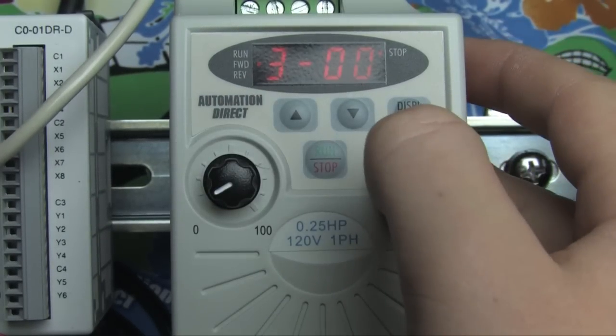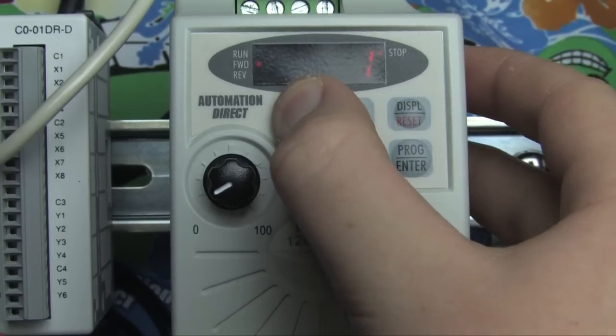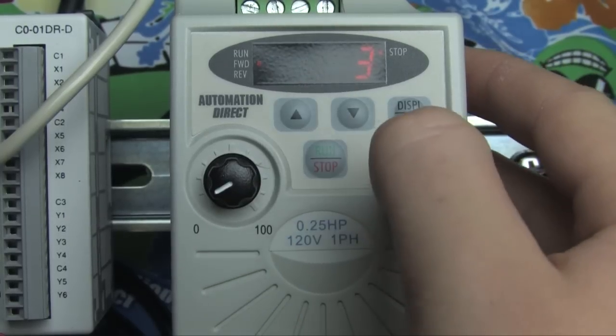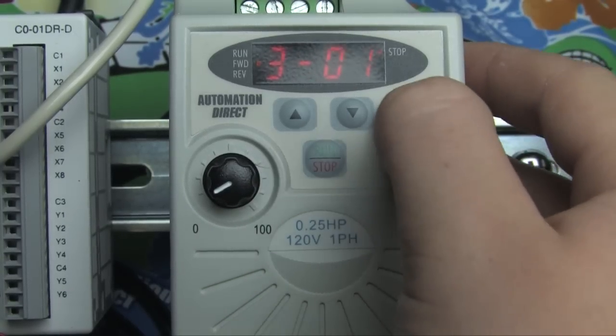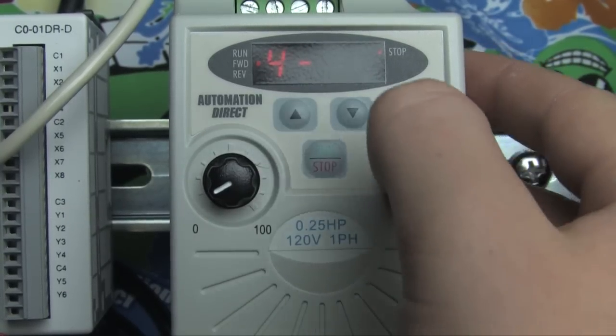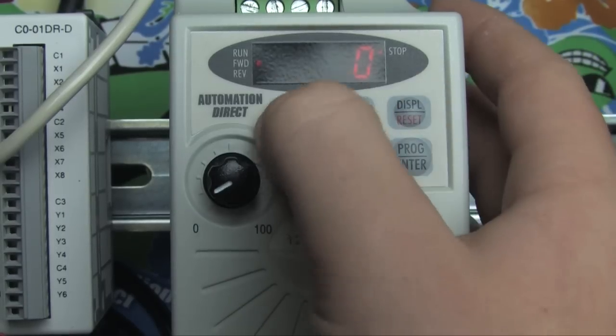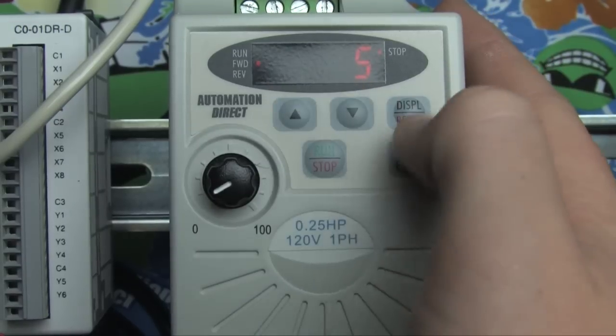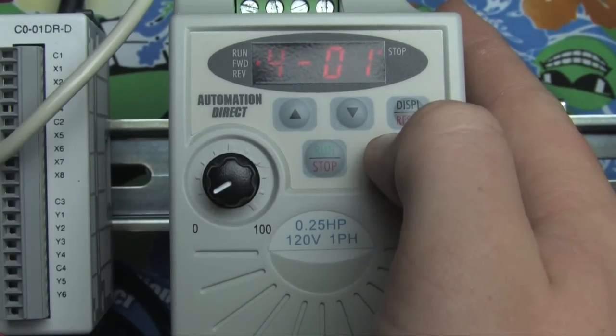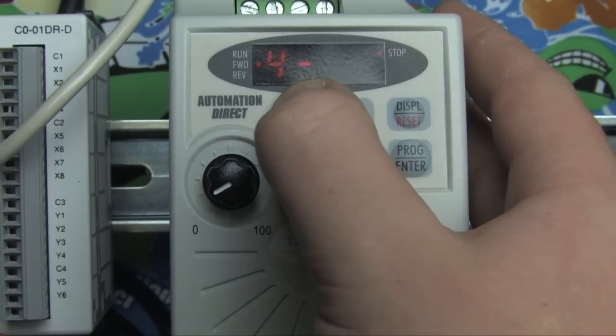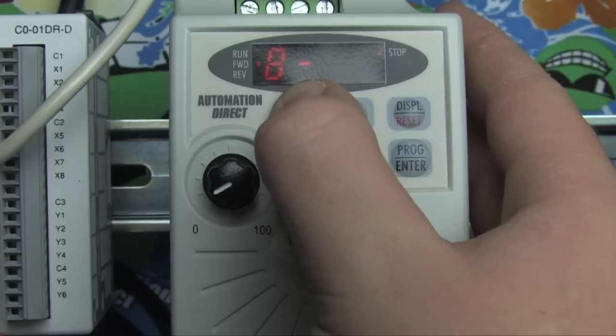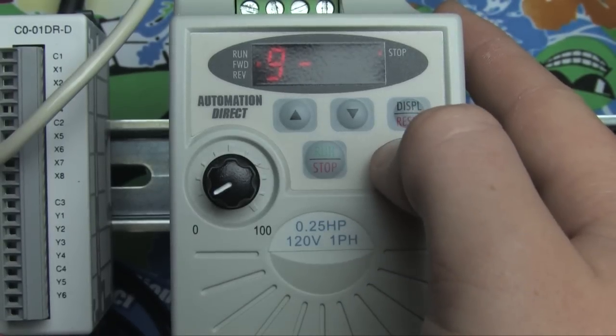Now, we need to set up the GS1 drive for Modbus communication. First, we need to make the drive controllable through Modbus. So we'll set parameter 3.00 to 3. This sets the source of operation to be determined by the RS-485 interface. Parameter 4.00 needs to be changed to 5, which tells the drive that the source of frequency will be determined by the RS-485 interface.